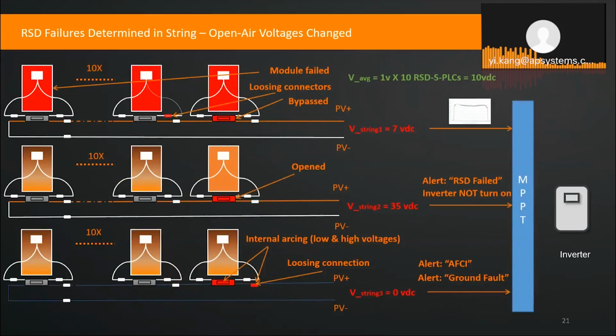This one just gives you an overview of how we'll do the troubleshooting and gives you a very easy step so you can get knowledge about what's going on with your system. We give the example. For instance, we have a 10-panel string, right? Each panel's safety voltage, we're assuming, is 1 volt. You're supposed to see, on average, the open-air safety voltage about 10 volts DC.